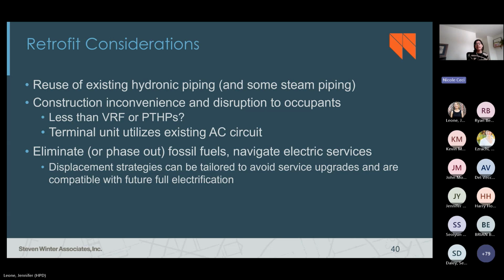We've seen plenty of cases where it's fine to use. That said, we've also seen some where the return line is a bit too small, or it's a one-pipe system and additional lines are needed. So it's a case by case item, but I think it's doable in a lot more cases than most folks realize. And if you can reuse any existing piping, that's a big win for minimizing disruption. Alternate options involve either cutting sleeves in everywhere or running new refrigerant risers and boxing out chases potentially. We're trying to minimize disruption and how invasive things are for residents.